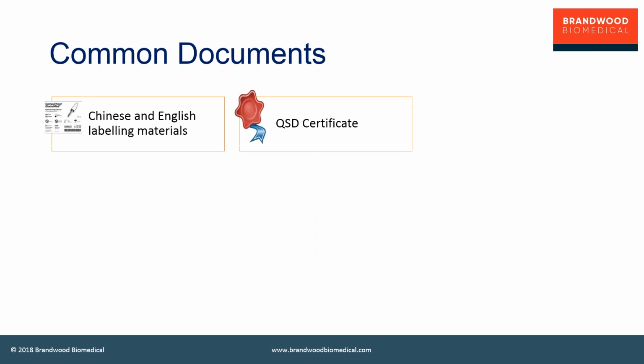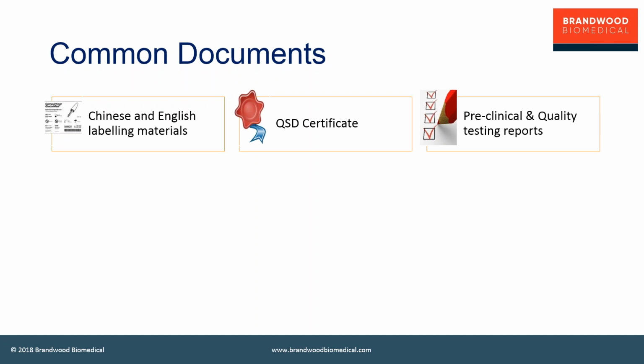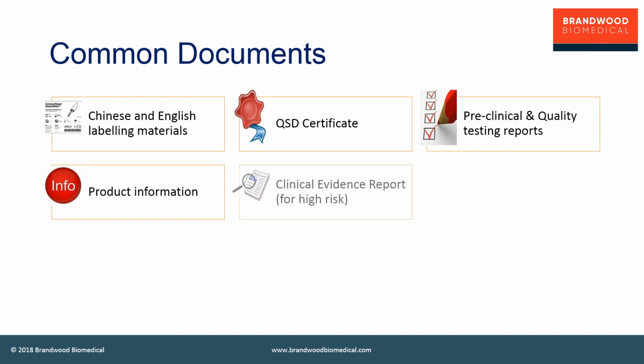You need a QSD certificate for quality systems. That's a certificate issued by the Taiwan FDA. You need to have your preclinical testing and quality testing reports. You need product information, instructions for use and product information. You need, for high-risk devices, to submit a clinical evidence report.